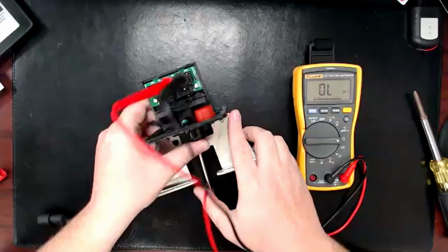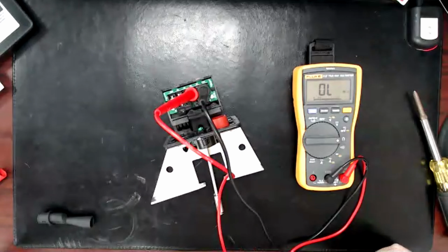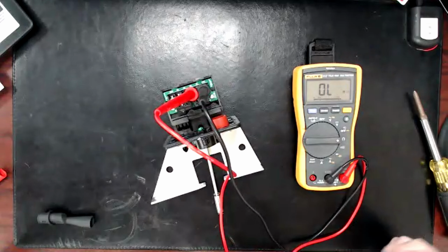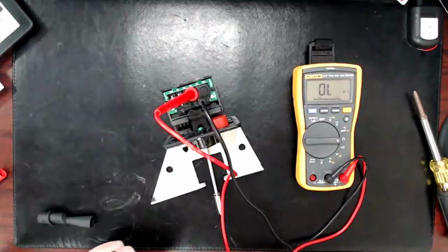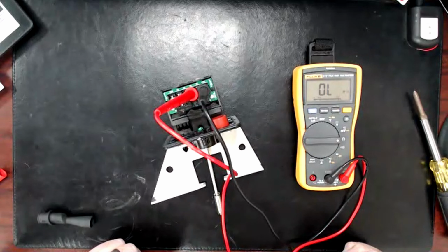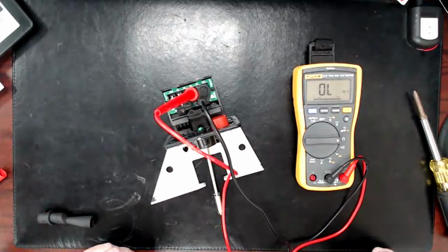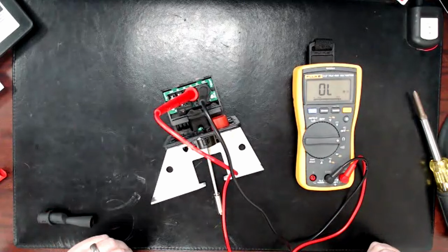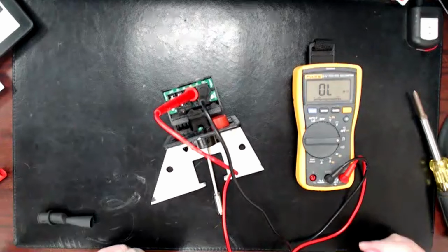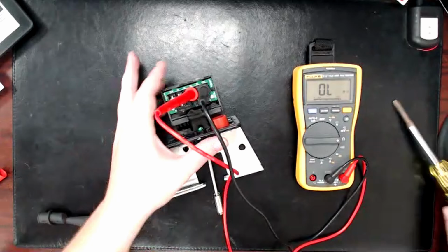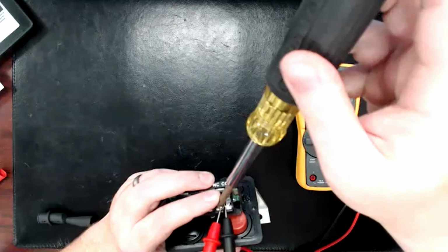But if you get that set, especially on a wall PIV or something where it's accessible to the public, if it's set too close to that line, that can actually cause some problems for the customer, because if someone, say, just walking down the street brushes their shoulder against this, then now it's sending their panel in and out of supervisory all the time, and that's going to be a nuisance.